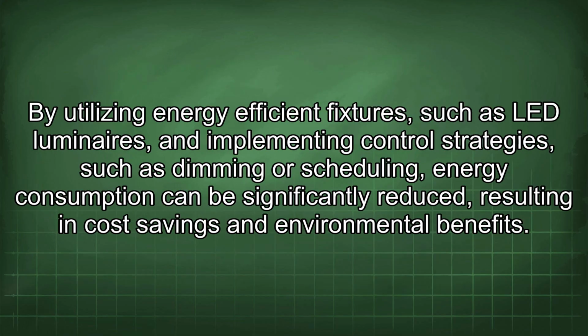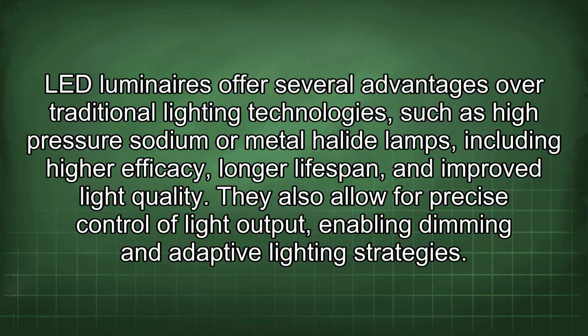By utilizing energy-efficient fixtures, such as LED luminaires, and implementing control strategies, such as dimming or scheduling, energy consumption can be significantly reduced, resulting in cost savings and environmental benefits. LED luminaires offer several advantages over traditional lighting technologies, such as high-pressure sodium or metal halide lamps, including higher efficacy, longer lifespan, and improved light quality. They also allow for precise control of light output, enabling dimming and adaptive lighting strategies.